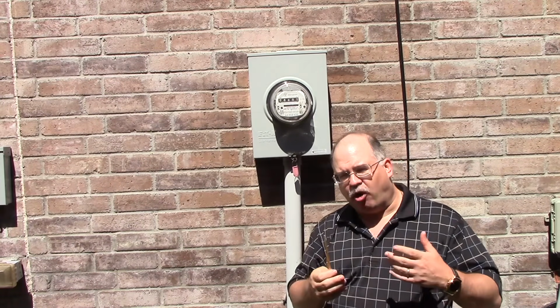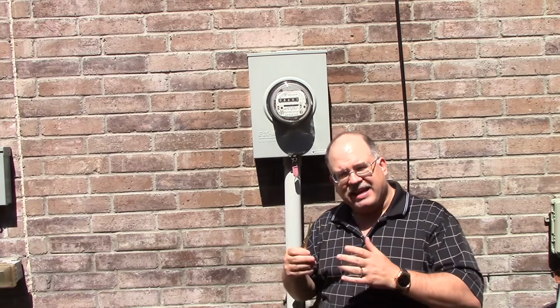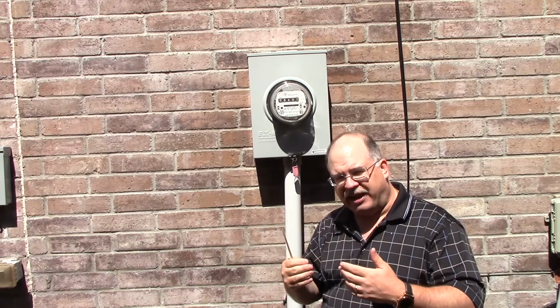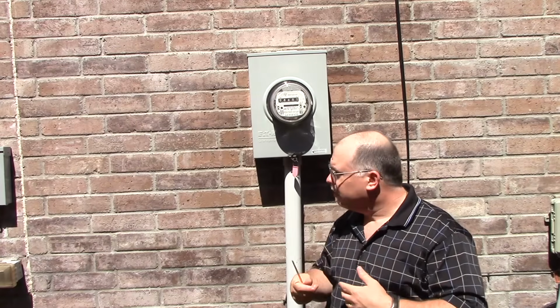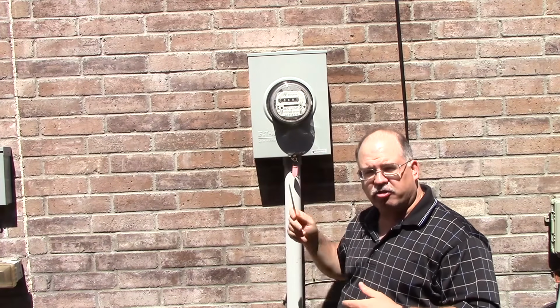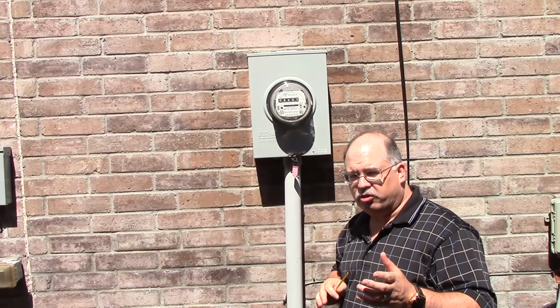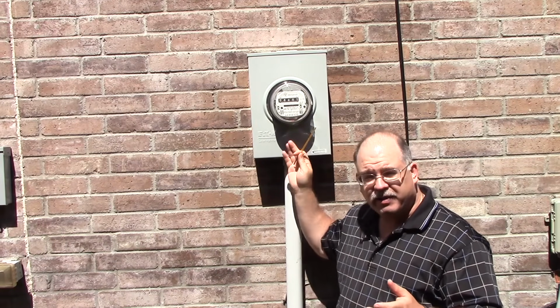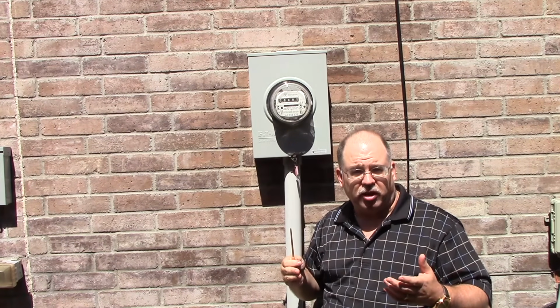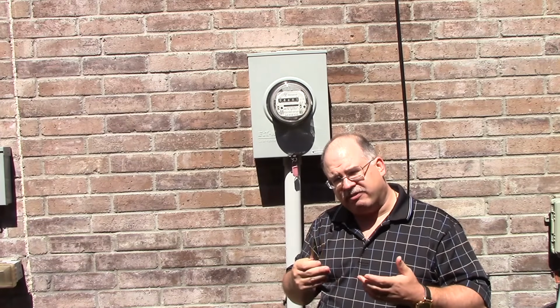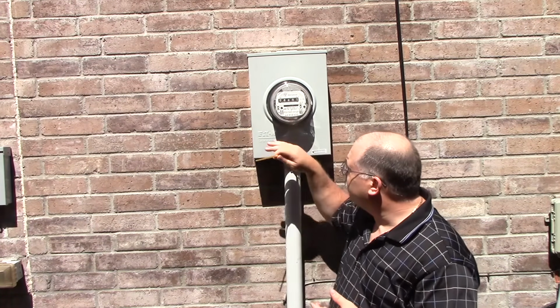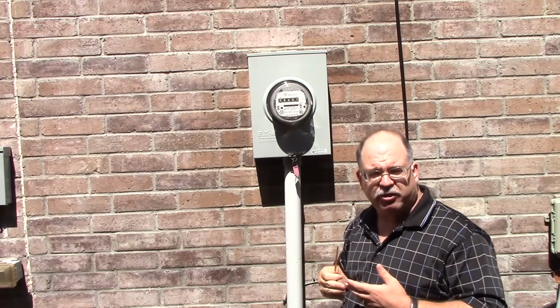But since we already have all the other details well known, now we're going to use that to help confirm the fact that we have a 200 amp service. In this case, this is a rectangular shaped meter, which is indicative of a 200 amp service. Now if this was square, then it would be indicative of a 100 amp meter, or maybe even a 125 depending on its age.